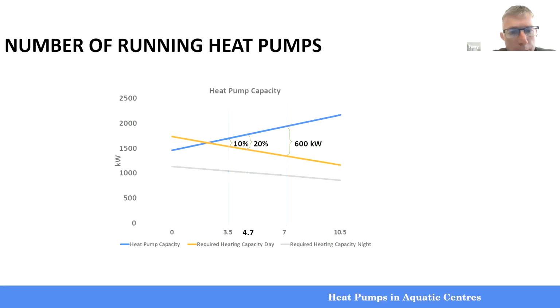This slide here, I explained to you that the blue line is basically the heat pump capacity. You'll notice that as the temperature goes up, the heat pump capacity goes up. And the red line is the required capacity of an aquatic centre, or this particular aquatic centre. And of course, as the day gets warmer, less heat is lost from the building, and so less capacity is needed. So this particular consultant was looking to design the heat pump system for an aquatic centre in Melbourne, and he chose the temperature of 3.5 degrees as the minimum temperature for that site. And he wanted 10% additional capacity, just in case, with the heat pumps at that point. So it just shows there that at 4.7 degrees, we had 20% more capacity than we needed. So at that point, that's when one of the 5 heat pumps would shut off.